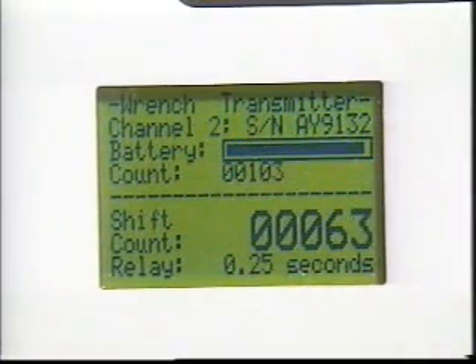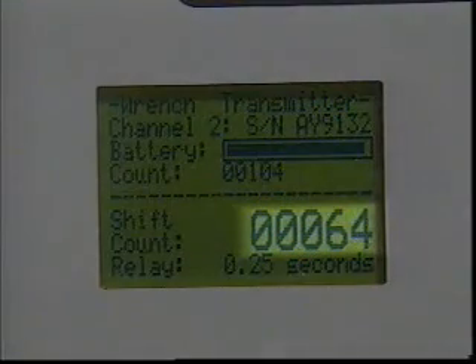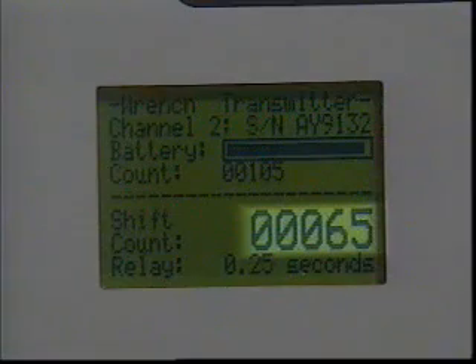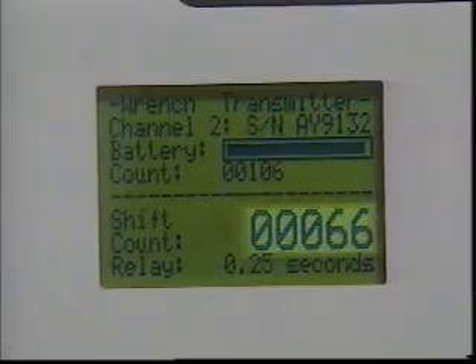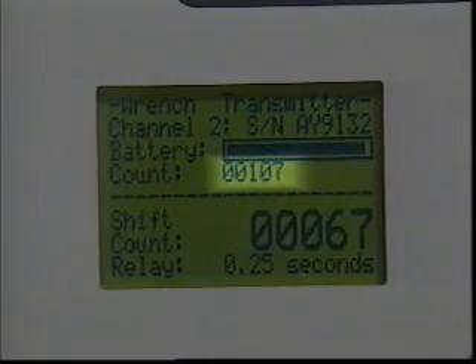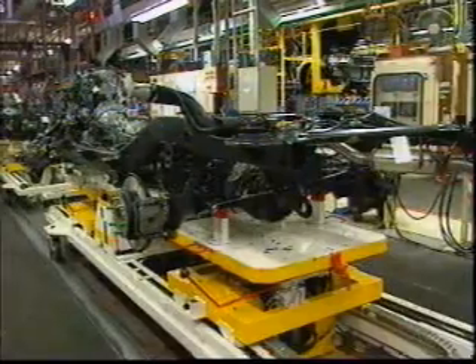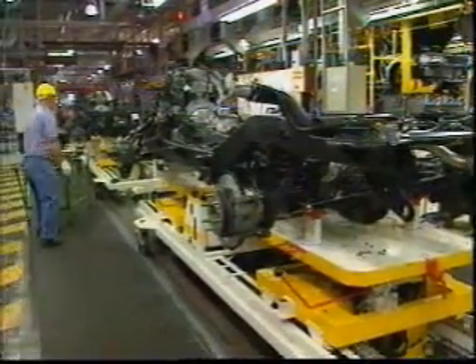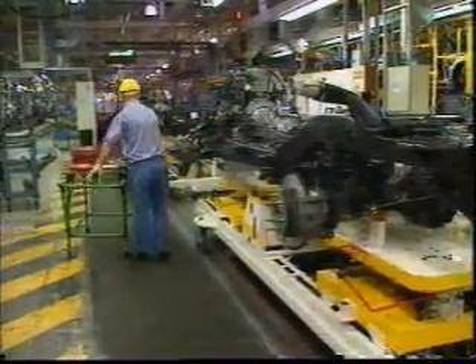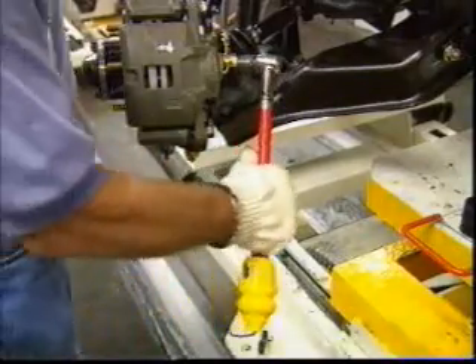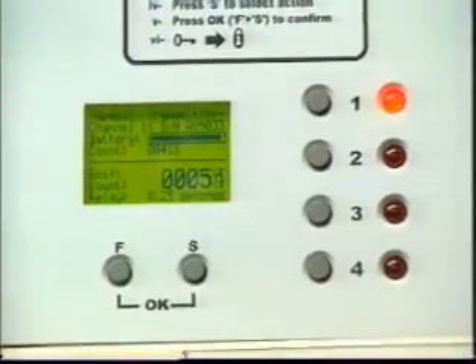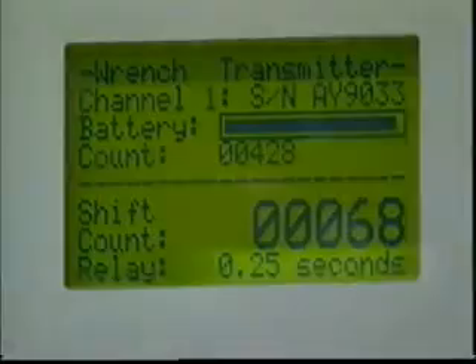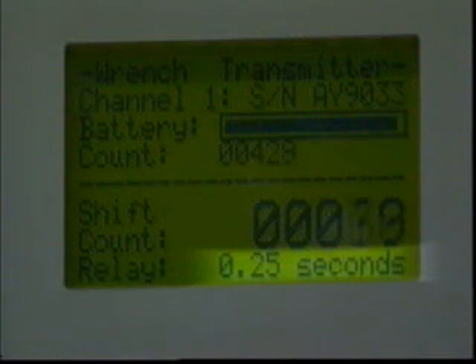The receiver counts at 2 levels. The shift count gives the number of tool operations in a given period or working shift. The background count gives the number of tool operations since the system was set up. This is a useful means of monitoring tool servicing or recalibration periods. The output relay times can also be adjusted between 1/4 of a second and 2 seconds, or can be disabled completely.